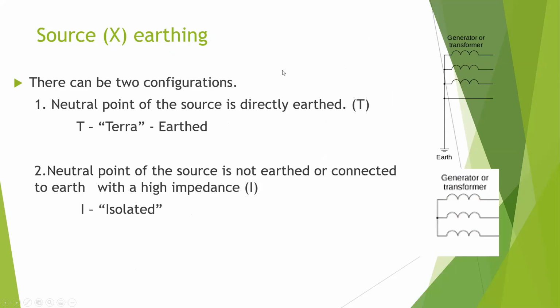For the source side, there can be two configurations. So now I am talking about only the source side. Earlier we talked about the installation side, but we are going to talk about that in detail in the next slide. Usually there are standard configurations for earthing. For a source, these are the two configurations of earthing. The first one is the source neutral is directly connected to earth. So this is called T, from Terra. Terra is, I think, Latin, a term for earth. Terra means earth.